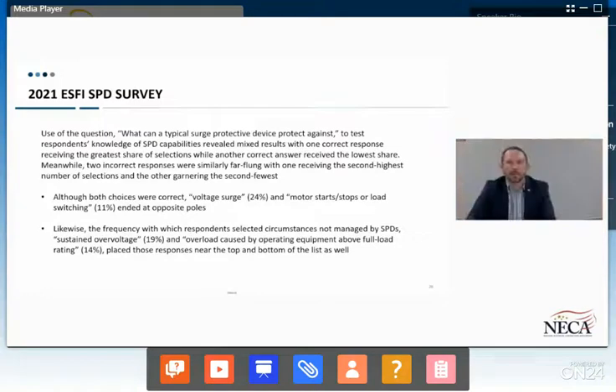Yeah, and I'd be remiss not to address another misconception out there. Our industry's SPDs do not protect against direct lightning strikes. They simply don't. That's a whole other industry, lightning protection systems. I think some folks, 16% I believe, said that that's what they do. Indirect lightning strikes coming through the utility and things like that, yeah, you have protection there from our industry. But a direct lightning strike is not an SPD.